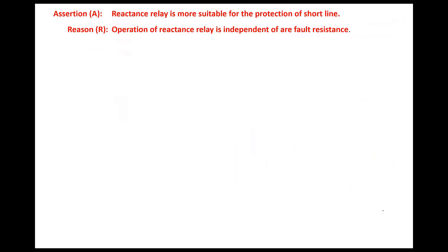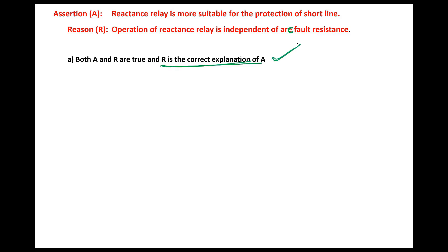Reactance relay is most suitable for the protection of short transmission lines because the operation of the reactance relay is independent of arc fault resistance. Arc is purely resistive, and short transmission lines have a higher probability of arcing. Both assertion and reason are true, and the reason is the correct explanation for the assertion.